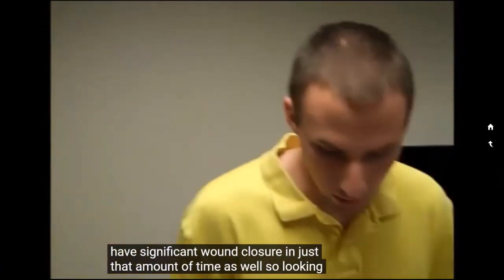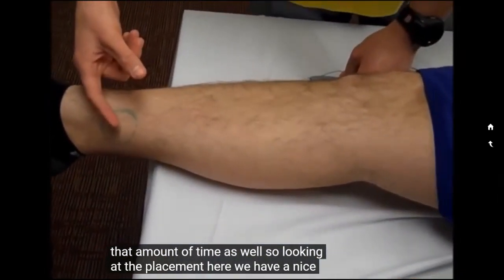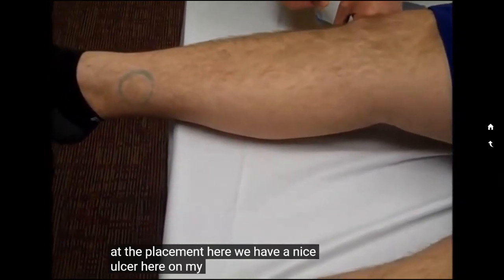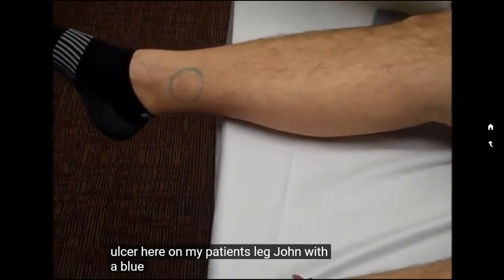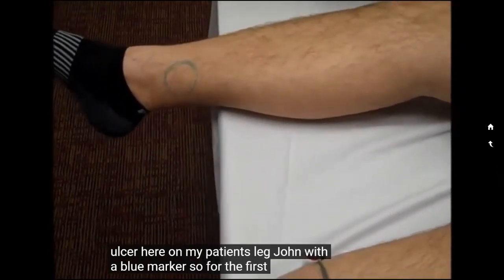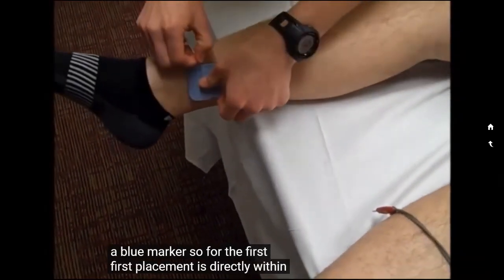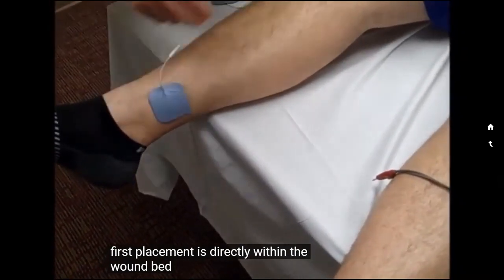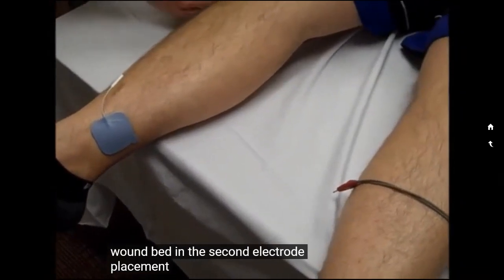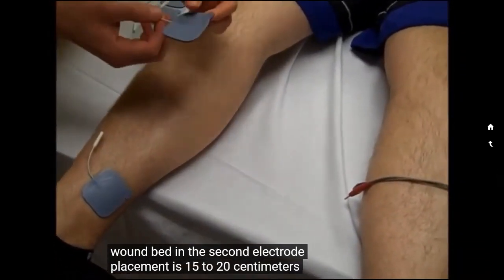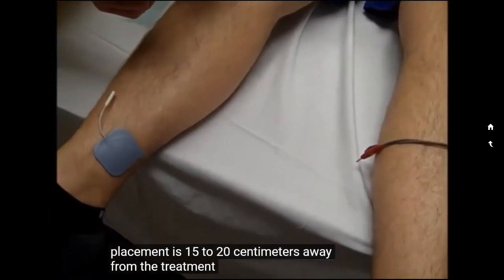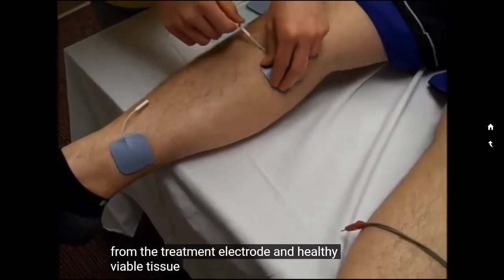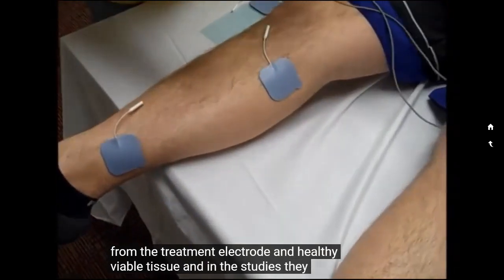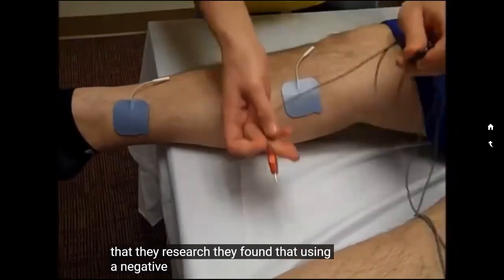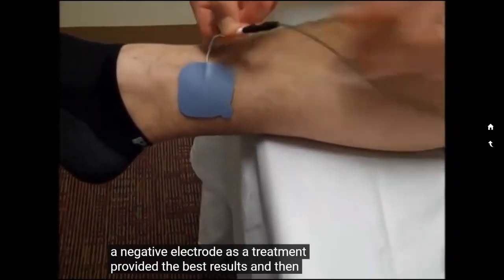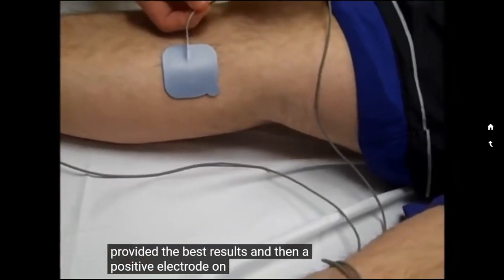So looking at the placement here, we have an ulcer on my patient's leg, drawn with a blue marker. The first placement is directly within the wound bed, and the second electrode placement is 15 to 20 centimeters away from the treatment electrode in healthy, viable tissue. In the studies that they researched, they found that using a negative electrode as a treatment provided the best results, and then a positive electrode on the healthy, viable tissue.